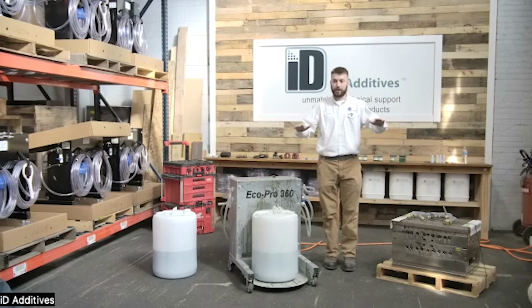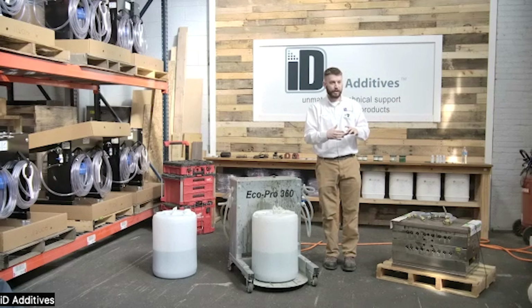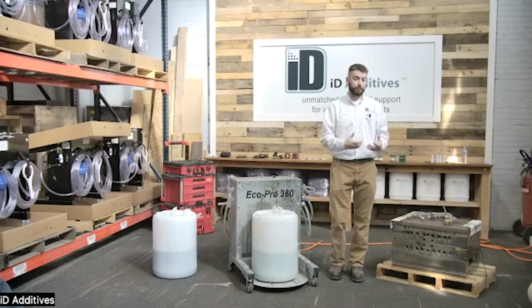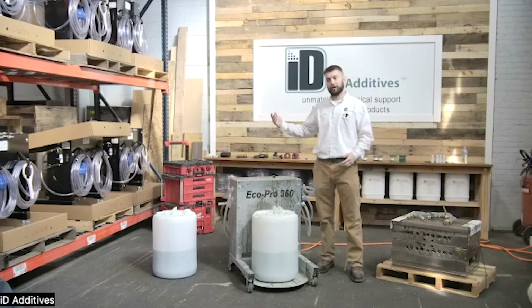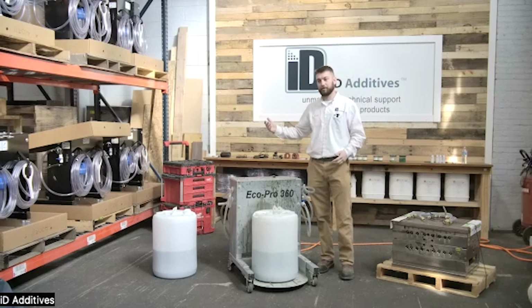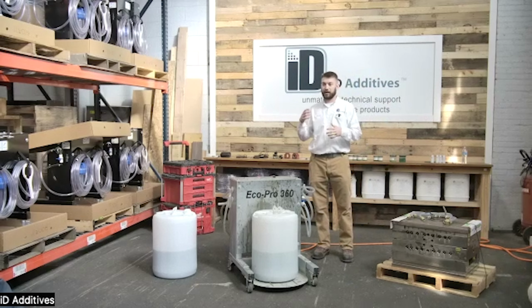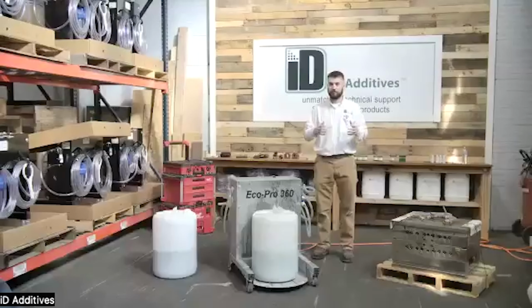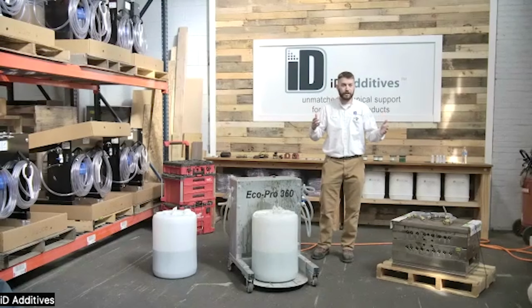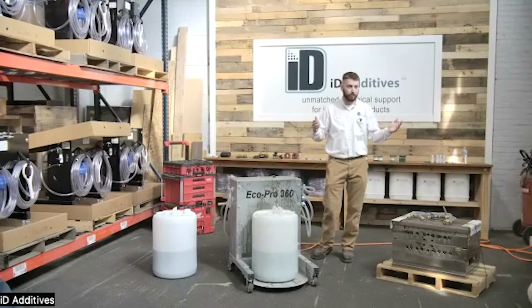I want the chemical to eat away at the calcium, the silica, the manganese, all that stuff. Once flow is achieved again, the pump will kick back on. Whereas an electric pump doesn't have those sensors, or most don't, and it's just going to keep hammering liquid until a line ruptures, and then you've got whatever acid you're using all over the place.